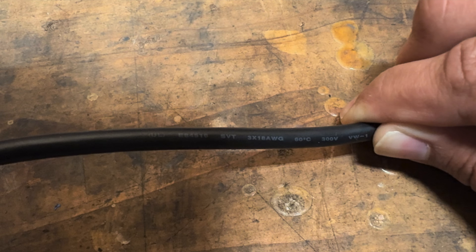Moving on to the receiver cable — this is a type SVT cable, which is a vacuum power cord. It is three times 18 AWG, so there are three number 18 copper wires in here. This jacket is rated for 60 degrees C and 300 volts.